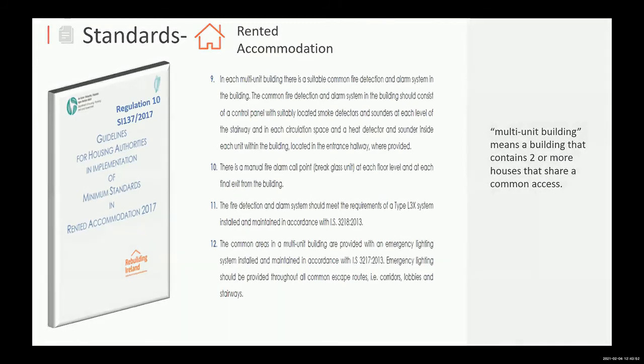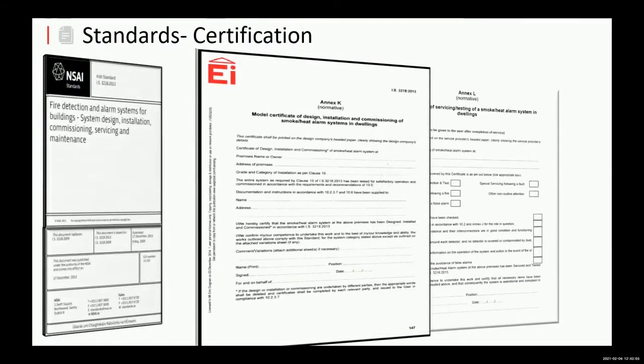That's basically just to cover the landlord area itself. Again, certification for the design, installation, and commissioning of smoke and heat alarms within the dwelling itself. That's there. Again, it's a cert that's more widely used now than it was before, and guys are more used to using it and want to use it. I suppose from an electrical contractor installation point of view, they feel a bit peeved because they now have to design the system more than likely, because the architect or the engineer just puts on the specification as per IS 3218 or grade D LD2. So it's left up to these guys to design systems.